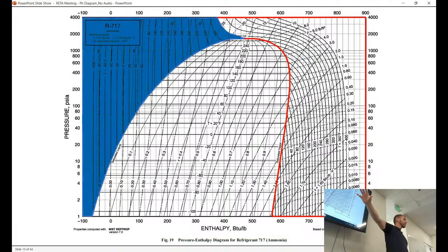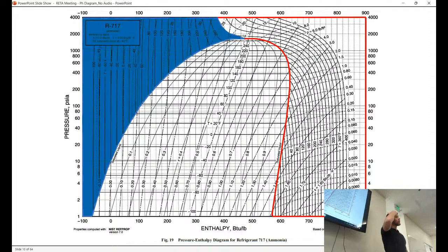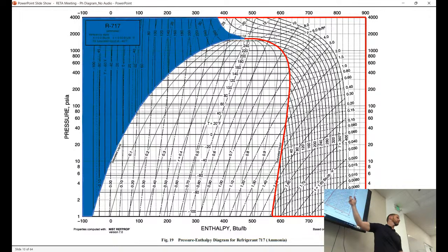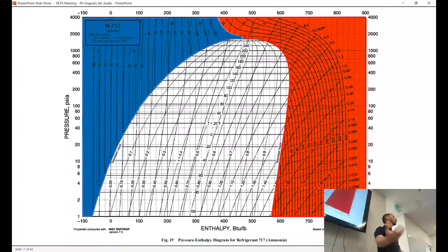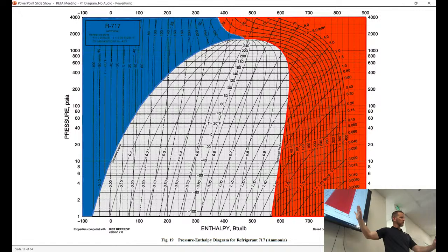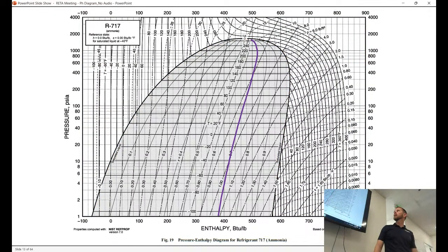Anything in that blue-shaded region is a sub-cooled liquid. Where do we get sub-cooling? The outlet of the pump could be sub-cooled. If you have a sub-cooler installed, certainly then you see sub-cooling. Maybe the outlet of a condenser if it's oversized — those would be typical spots. So if that's saturated, that's sub-cooled. What do you guys think this other region is going to be? Superheated, yeah. Where are we always superheated? Outlet of the compressor. We can also be superheated — but not always — at the outlet of the evaporator or the inlet to the compressor in a DX system.